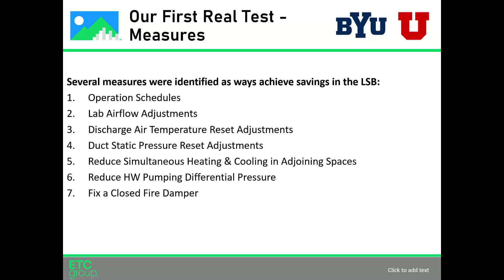We added hot water pumping differential pressure resets where we hadn't had those before. We also found a closed fire damper causing air to backflow through smaller ductwork, and fixing that one issue saved us quite a bit.